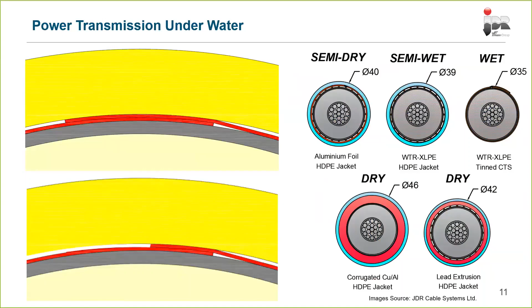We also need to worry about cable temperatures. When drawing a high amount of power through a cable, there's a propensity for it to heat up. We do this through computational modeling, but for tricky scenarios, especially with other heat sources in the environment, we'll do some FEA modeling. We put current through the conductors and predict how hot the outside of the cable will get, and how heat distributes through the area, depending on the environmental temperature around it. If you get a collection of cables together, heat can build up because they don't have as much heat dissipation.